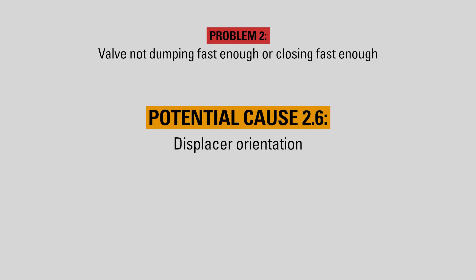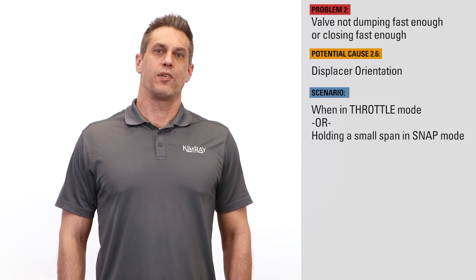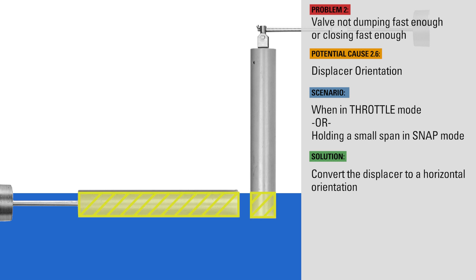When in throttle mode or trying to hold a small span in snap mode, the ideal displacer orientation is horizontal because you get more change in displacement per fluid level change, so the controller reacts sooner than it would in vertical orientation.